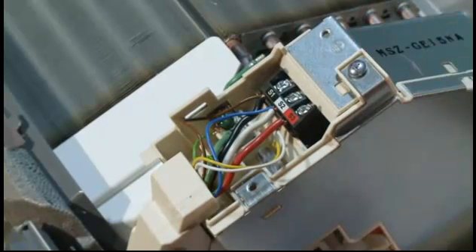The condensate tubing could be kinked, or your receiver filter screen could be stopped up. The second reading we could get would be the same voltage at the S2 and S3 on the indoor unit that we got on the outdoor unit, 26 volts DC.